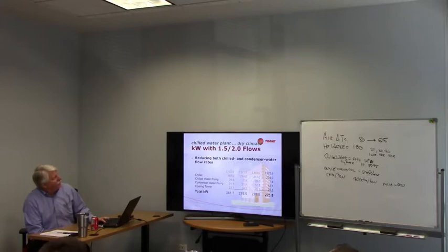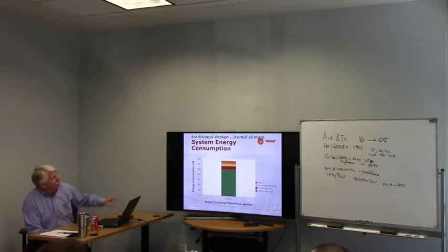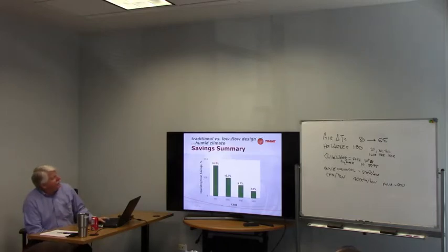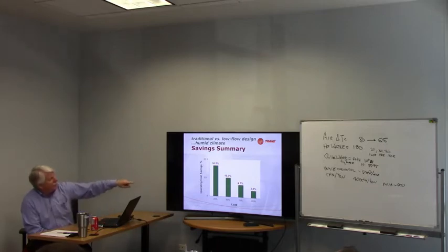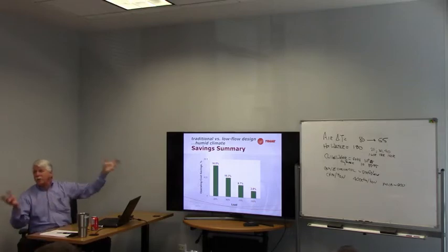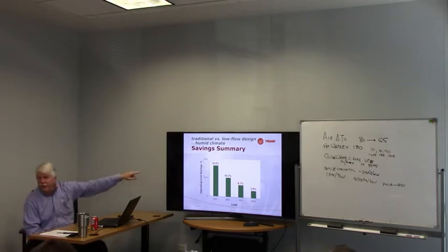Reducing both chilled water and condenser flow rates, you can optimize it and end up where they are there. And this just talks about the tower kW, the condenser pump kW, and the chilled water pump. You can see here at our original design of 10 degrees on both systems, you've got that. And when you go low flow, this shows the kind of energy consumption you can save. And this has to do with the load in the system. So before, everything I was showing you was at 100% load, at full load. At part load, it even gets more savings.